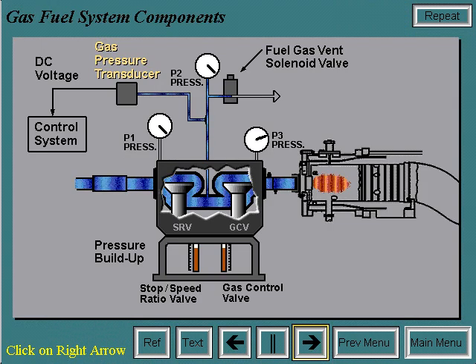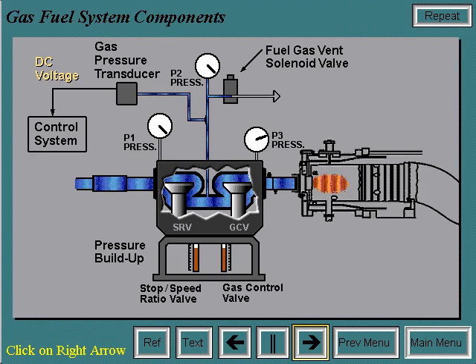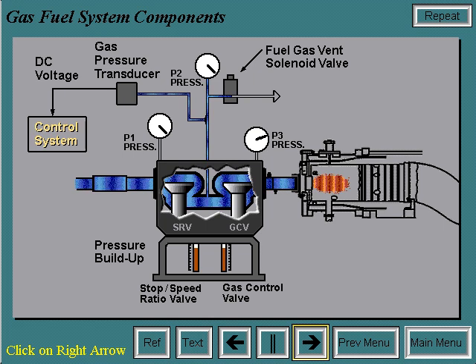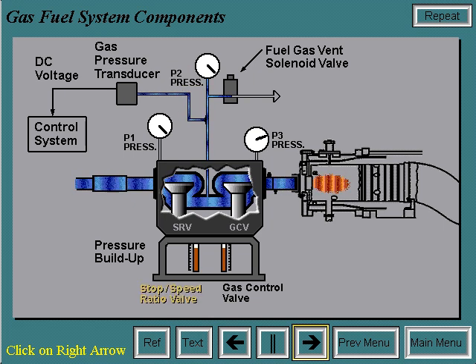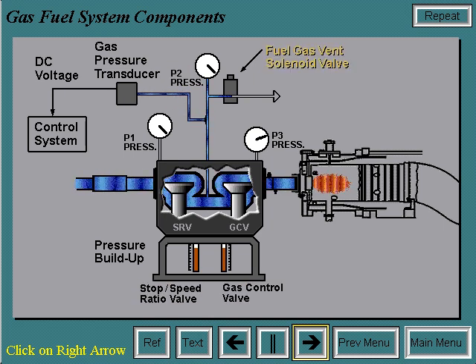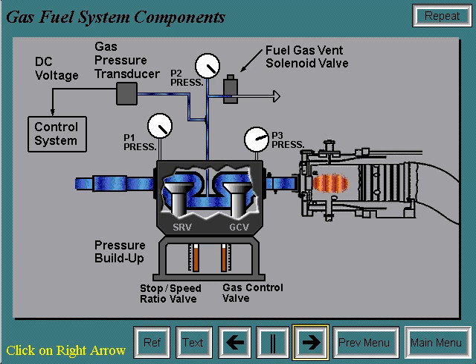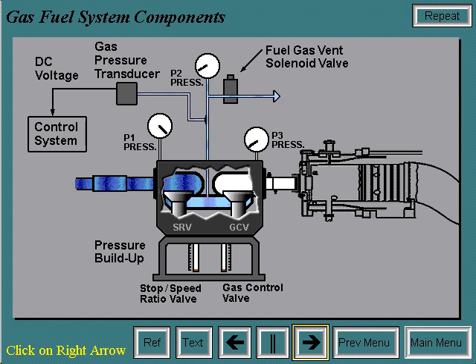The fuel gas pressure transducer has a DC voltage output directly proportional to pressure input in PSIG. This transducer provides the control system with a feedback signal for the operational fuel gas pressure, or P2 pressure, between the stop speed ratio and gas control valves. The fuel gas vent solenoid valve vents the volume between the stop speed ratio valves and gas control valve when the solenoid is de-energized. This valve is closed during operation. When it is open, it ensures that during the shutdown period, fuel gas pressure will not build up between the stop speed ratio valves and that no fuel gas will leak past the closed gas control valves.